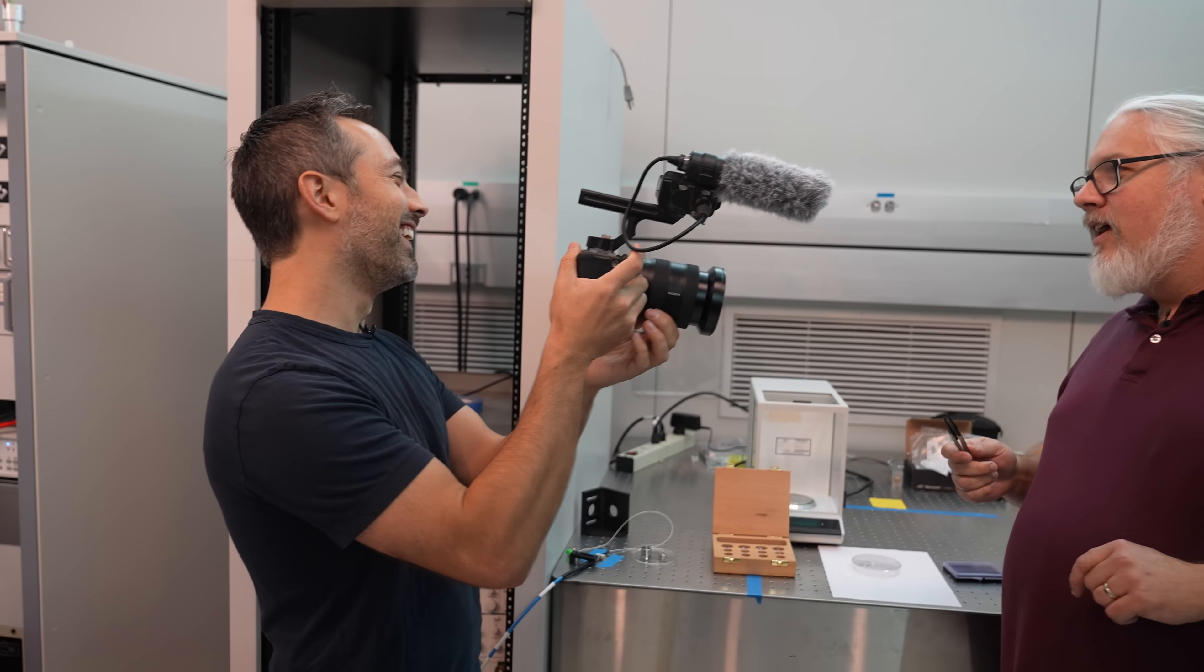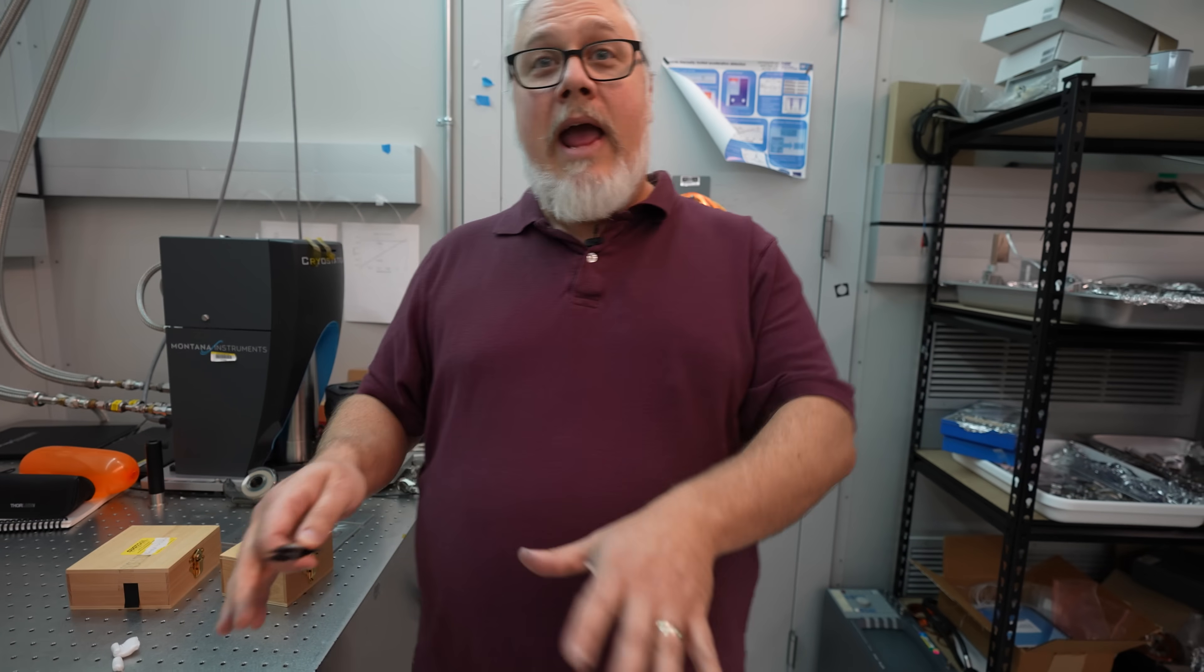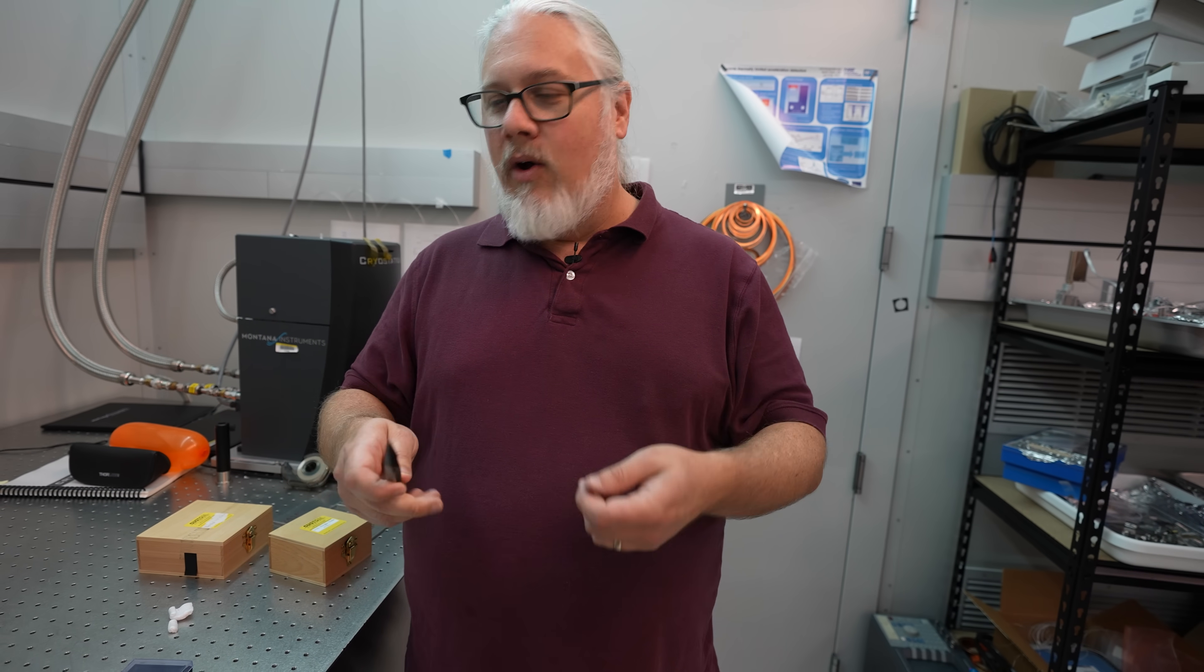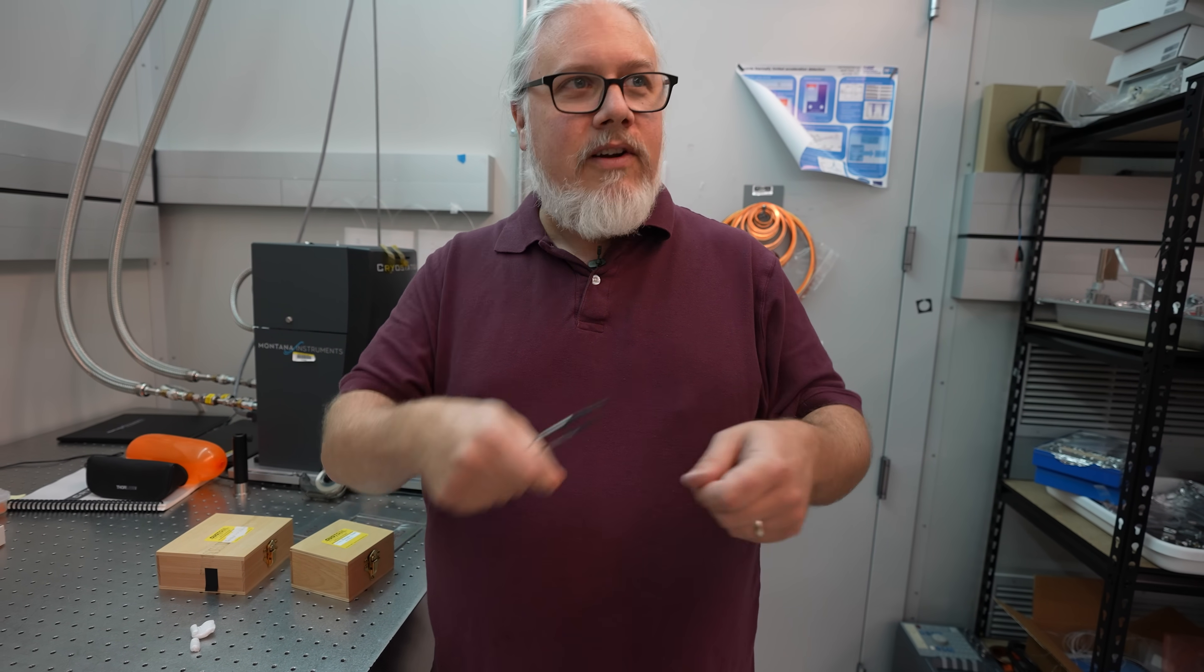If you have a speck of dust on here or something like that, it can be a problem. If it's a big speck of dust, so every time we do weighings with these, we'll take a lint-free cloth and a brush and clean them off a little bit.